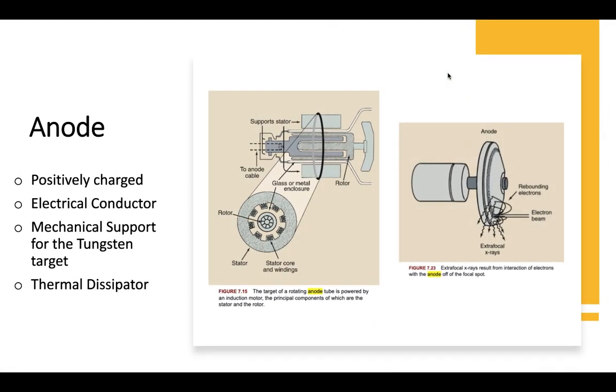The anode is the positive side of the X-ray tube. It is made from molybdenum, copper, tungsten, and graphite. It receives electrons emitted by the cathode. The anode is a mechanical support for the tungsten target. The rotating anode allows for the electron beam to interact with the larger target area. The rotating anode rotates during exposure and helps to dissipate heat.